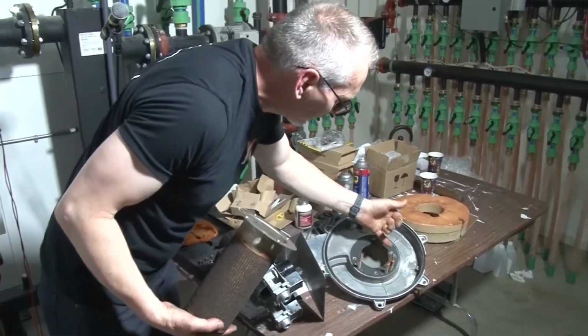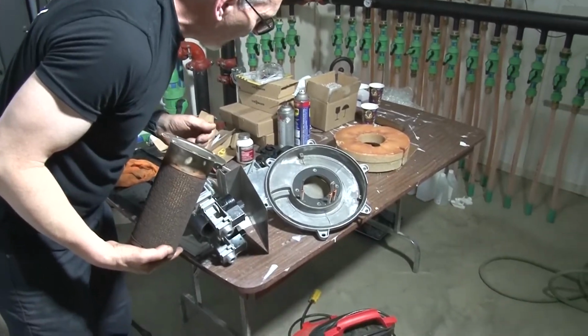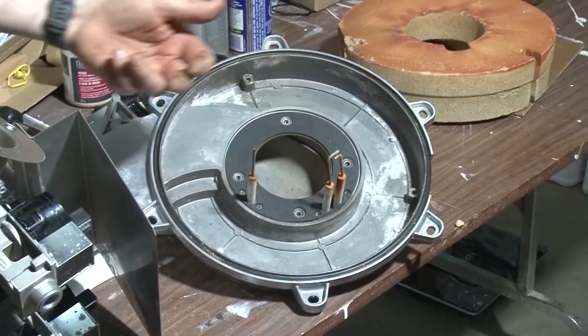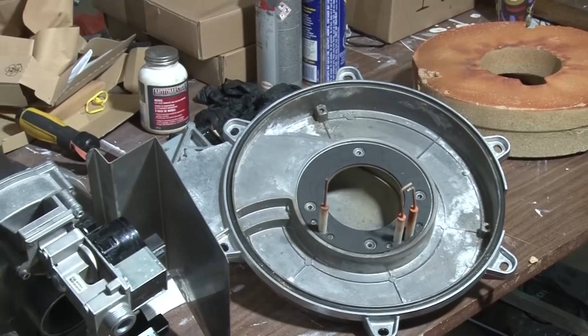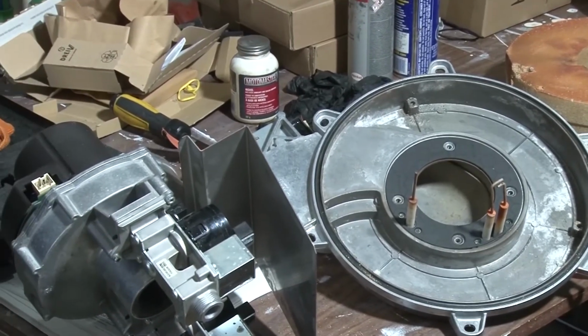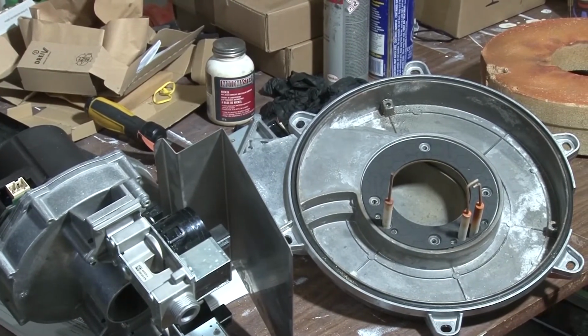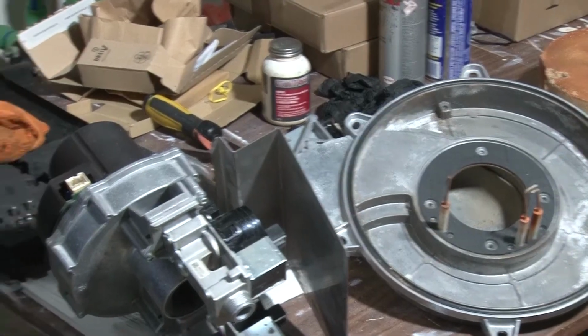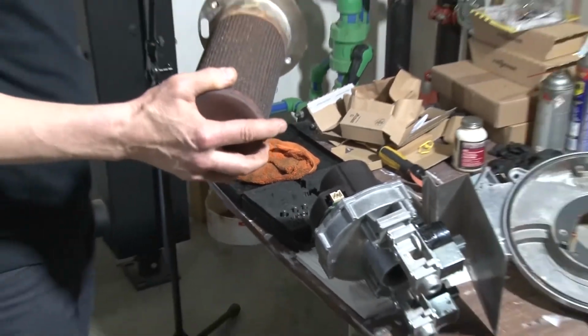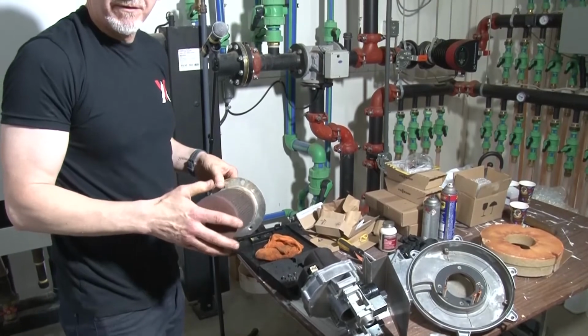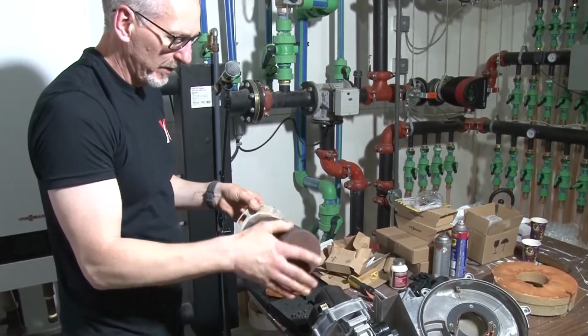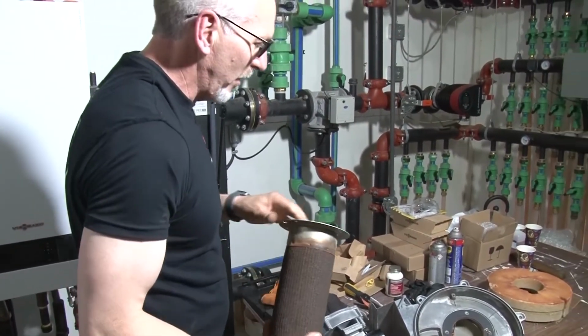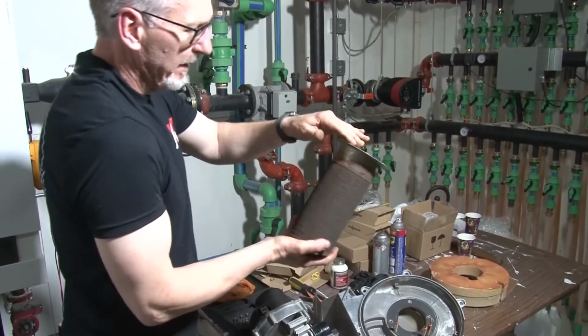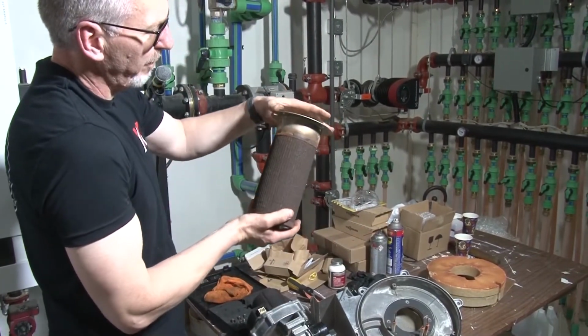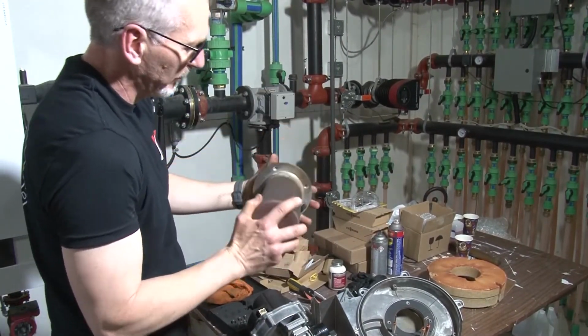And we're looking for cracks on the burner gasket here. Any little hairline fractures can be a problem because what you'll have is flue gas basically escaping from that area and it could light off. And now you're going to have a distorted flame, which can cause a problem obviously for your flame ionization, etc. So we want to make sure that we don't have any cracks in this area. We got a nice flat surface on that burner flange. It's not warped or anything like that. This one looks really good.